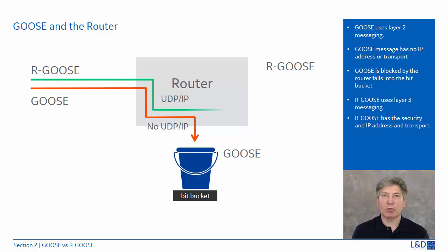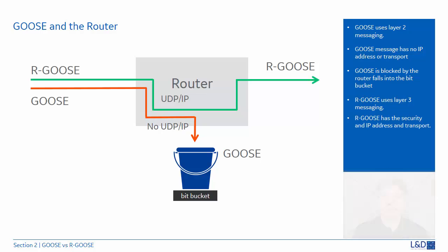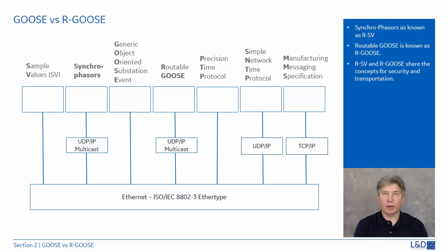The Rgoose is a multicast Layer 3 messaging service designed for use in a wide area network environment. It has UDP and IP headers assigned to it, which allows the Rgoose message to pass through the router's firewall. Here we have a list of protocols available: Sample Values (SV), Synchrophasors — now known as Routable Sample Values (RSV), the GOOSE message, the Routable GOOSE (Rgoose), PTP Precision Time Protocol and IEEE 1588, SNTP Simple Network Time Protocol, and MMS Manufacturing Messaging Specification. The only difference between the GOOSE and the Rgoose is the UDP/IP header. The guidelines for synchrophasors regarding security and transportation have been adapted to the Routable GOOSE. In the next section, we'll take a look at how we secure the Rgoose.